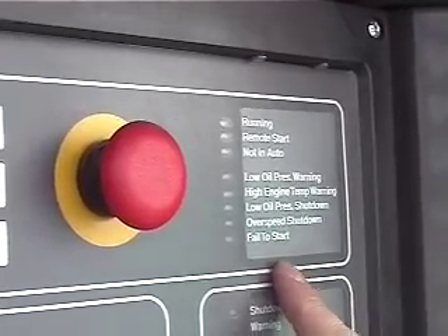This is fail to start. How it operates is that anytime it attempts to start, it wants to see engine speed within 75 seconds. If it doesn't, it locks itself out and shuts down. Obviously, if it hasn't started, there's something wrong, and it goes through crank cycles of 15 seconds.